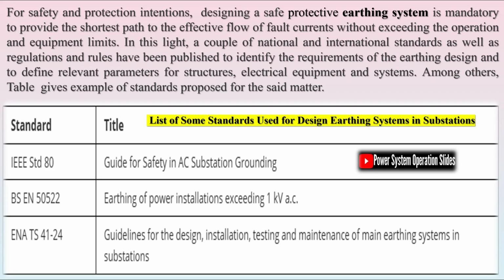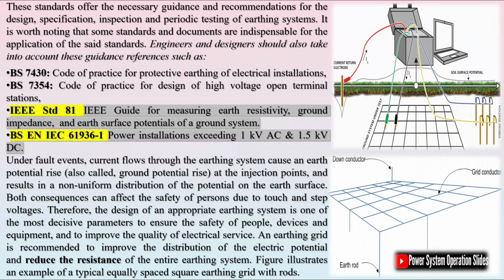As shown in the figure, all metallic parts are earthed to prevent accidental contacts by workers with energized elements. In addition, a layer of surface material, gravel in the figure, of high electrical resistivity is usually used in substations. This layer can help in limiting the body current by adding resistance to the equivalent body resistance.